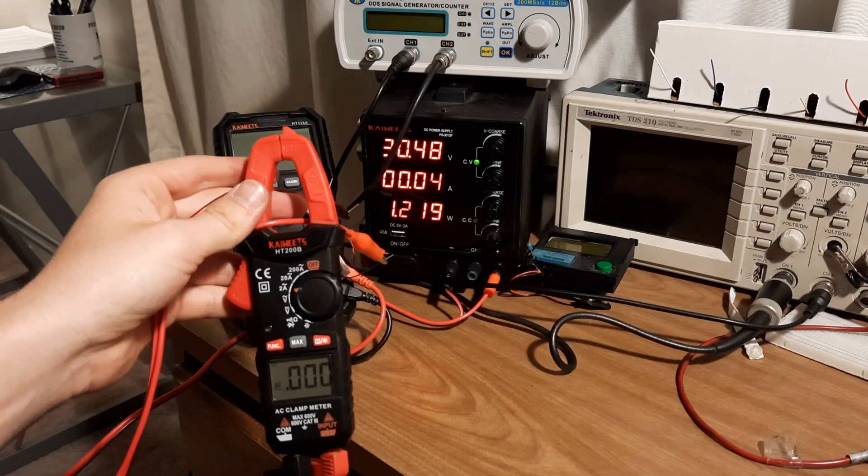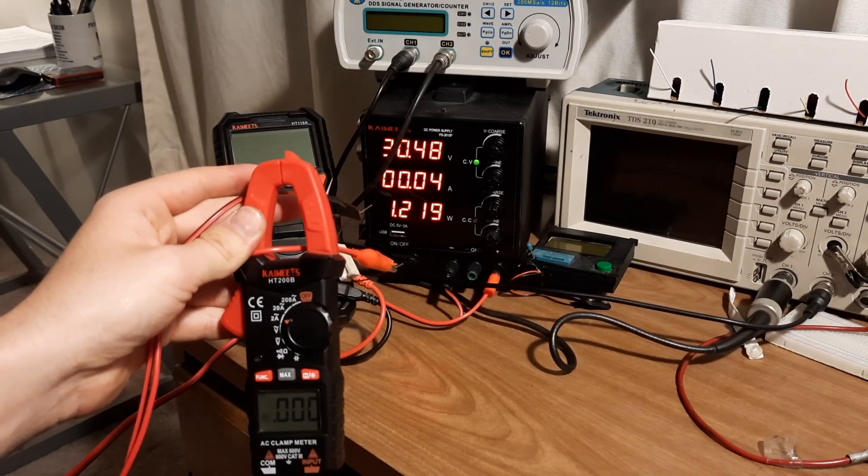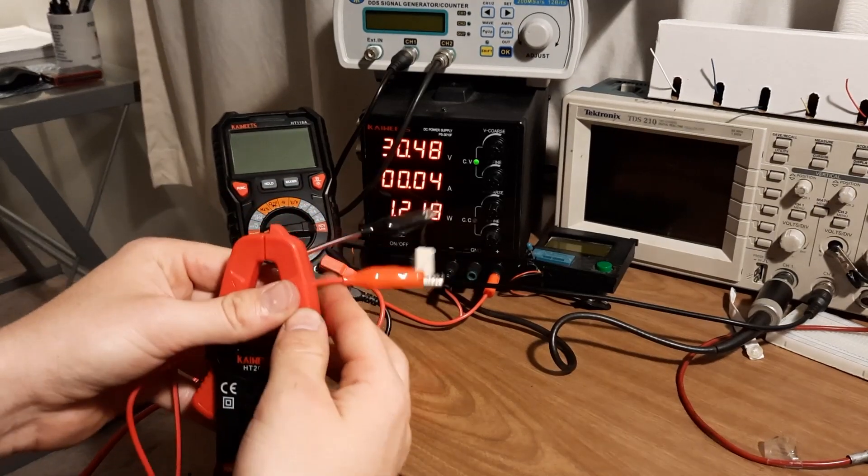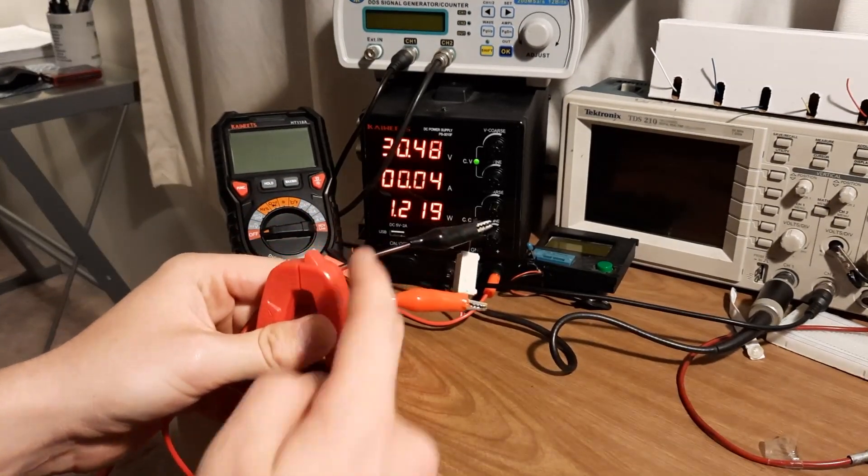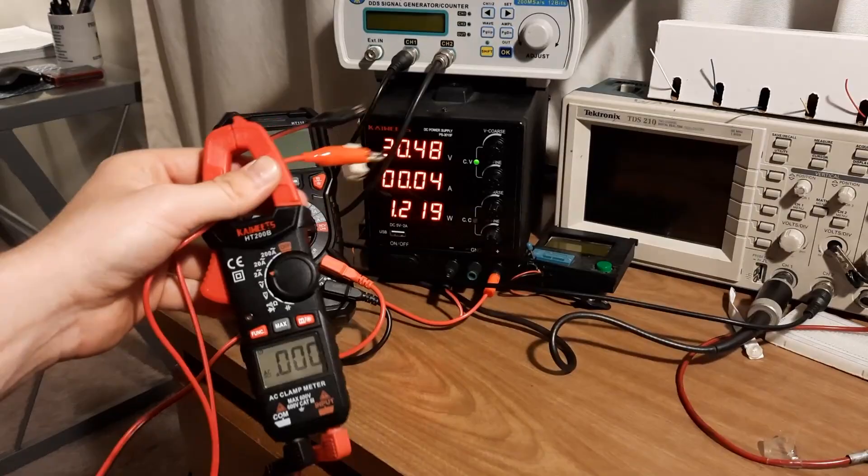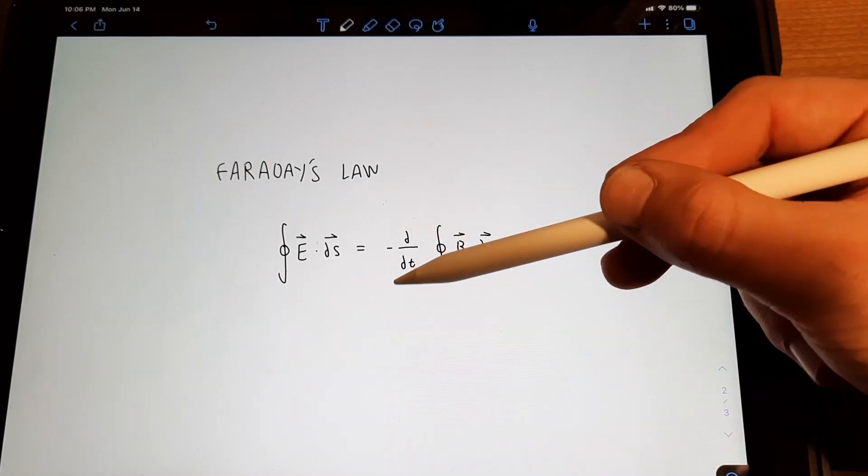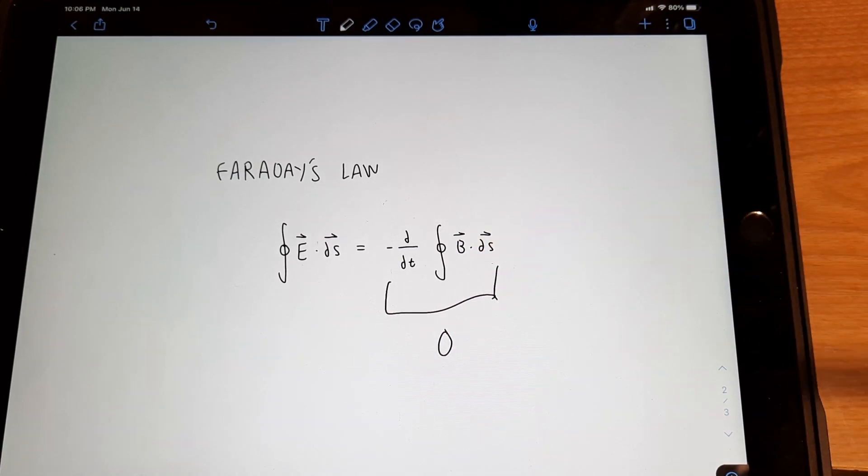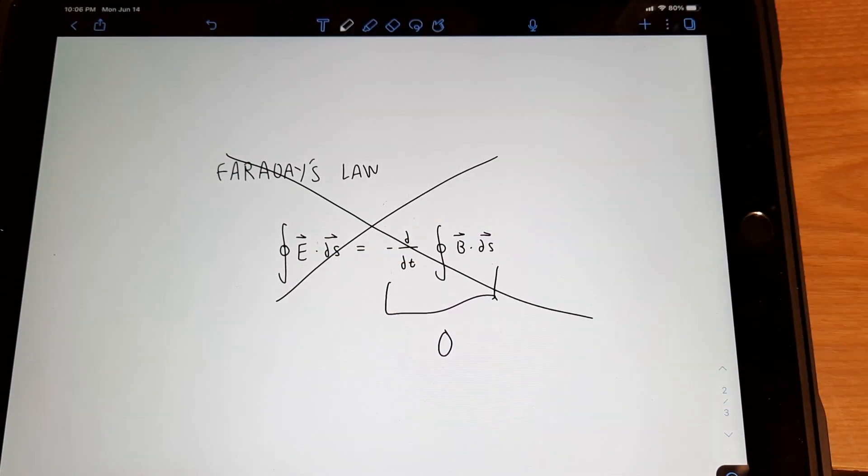This method of measuring current with a clamp meter works all fine and good when you're using a changing magnetic field that comes along with AC current. But how about DC current? Where the magnetic field around this wire stays constant and doesn't change? We can't use Faraday's law because this whole side of the equation just becomes zero, because that magnetic field is not changing. So that rules out the possibility of using that.